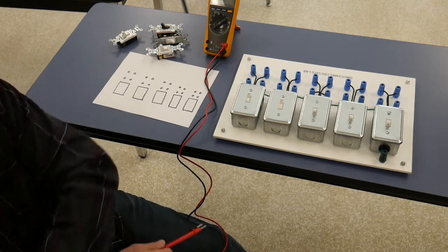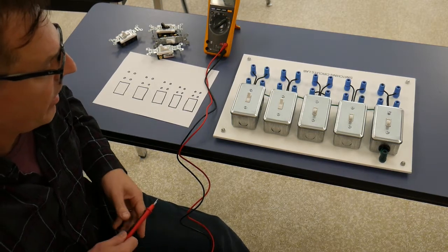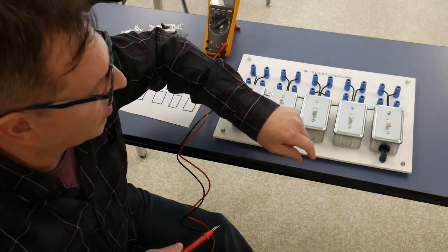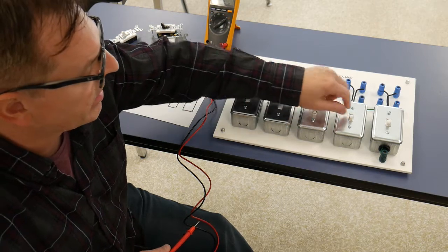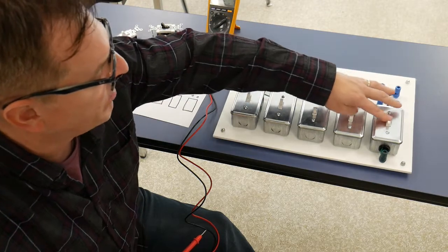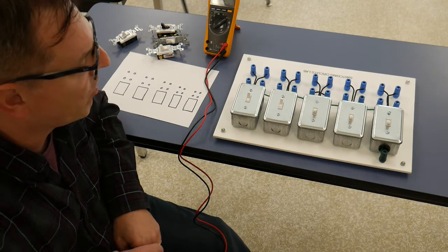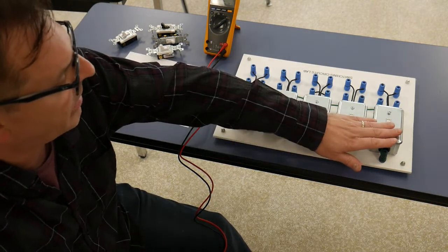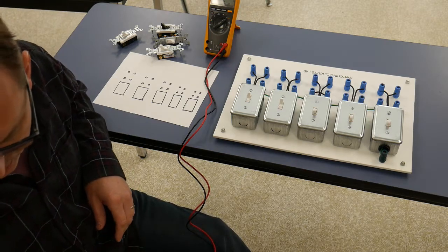So I need to be able to determine and isolate which switches are what. Now the first guess I can look at right off the bat, and it might be a little hard to pick up on the video itself, is that this switch here is labeled on and off, and this one actually has a dot and a blank. Because those have indications right away, that tells me that they are not a three-way or a four-way switch. So we can identify which one is a single pole and which one is a double pole single throw switch.